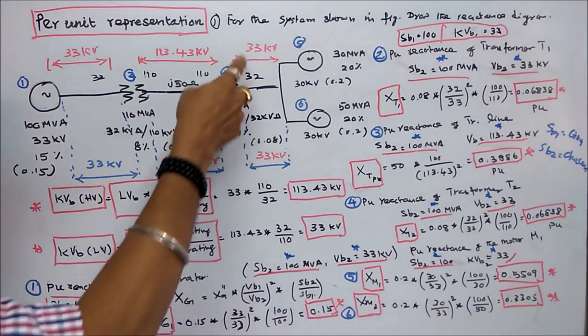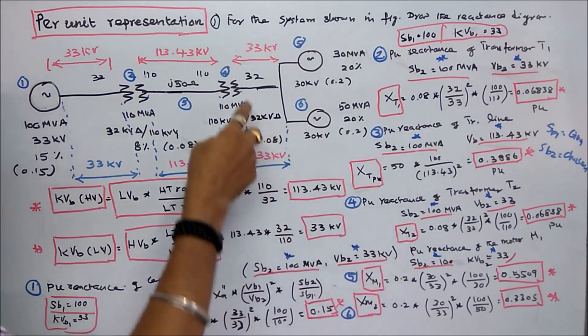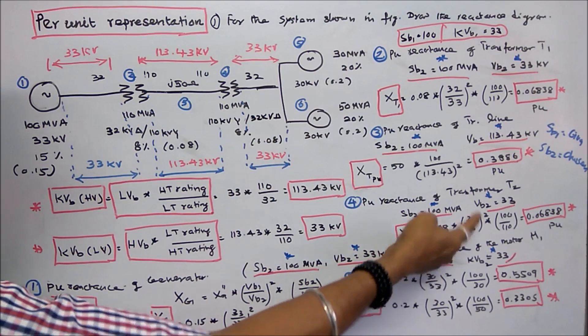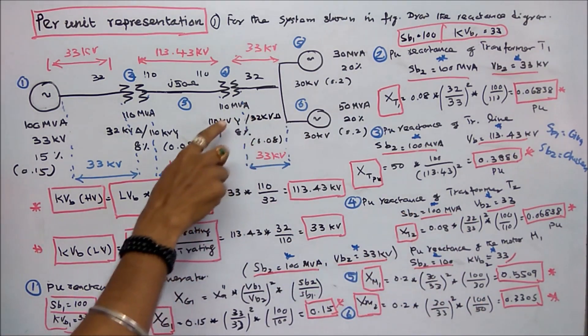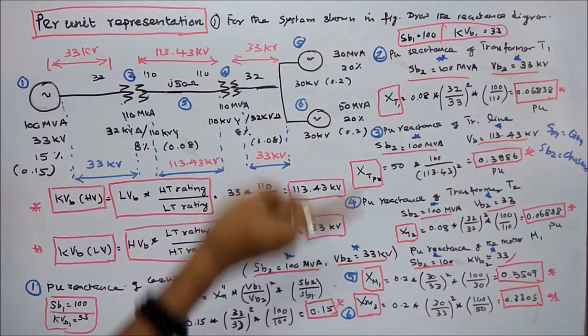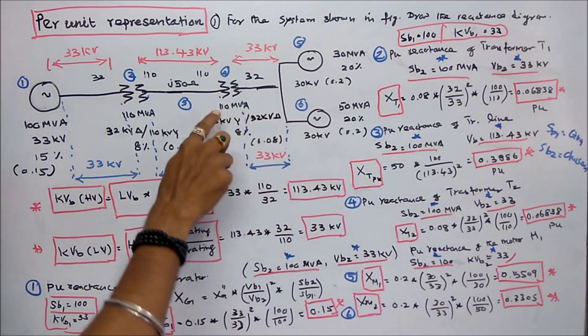The fourth is per unit reactance of transformer T2. SB2 is 100 MVA and VB2 is 33 kV. Using the same formula, per unit reactance equals given value 0.08 into (VB1/VB2) squared, which is (32/33) squared, times SB2 100 divided by given value 110. That equals 0.06838 per unit.